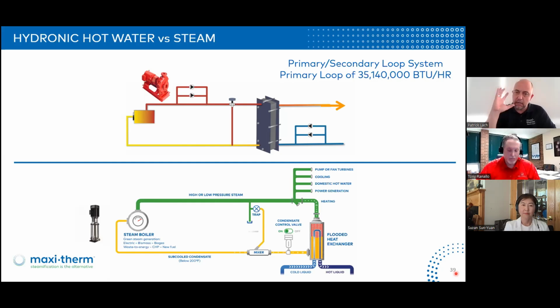So keep that in mind, the concept Tony explained, versus hot water for a 35 million BTU loop. That's a job that came out for bid in a federal prison in New York State, I will say 7 years ago. And we took that spec and we decided to challenge if they would go primary loop steam instead of a high temp hot water. So next slide.